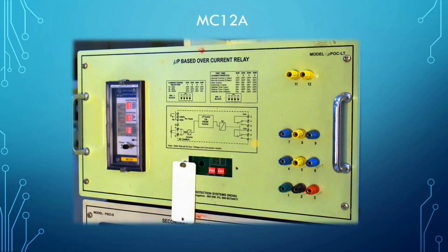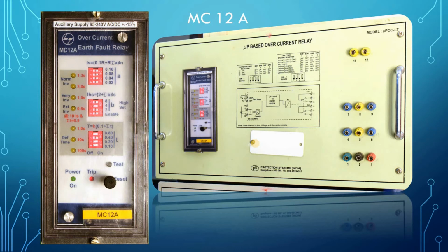Here, in the numerical overcurrent relay, it is different. In the electromechanical overcurrent relay, that is a mechanical constant, and TMS cannot be more than 1. But here TMS can be more than 1 and also less than 1. So there is a wide range of time setting multiplier, a wide range of trip time characteristics, a wide range of current setting, as well as the high set. These are the extra advantages of the MC12A relay, the numerical relay.